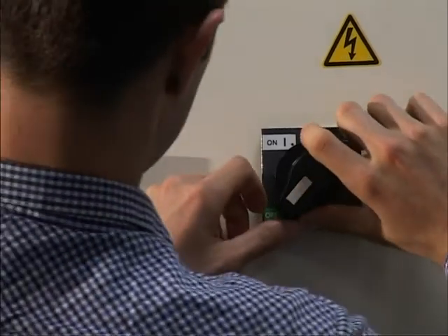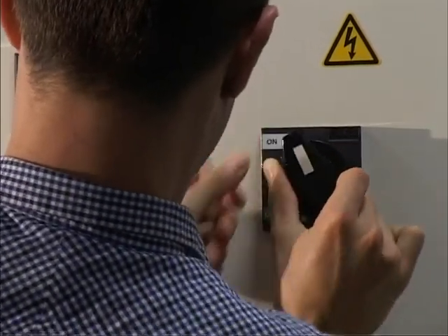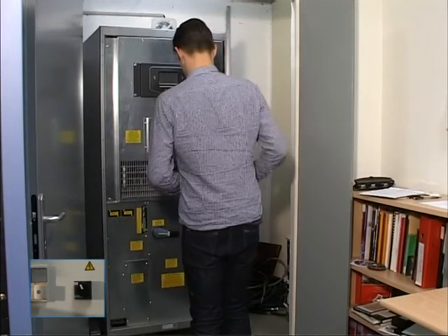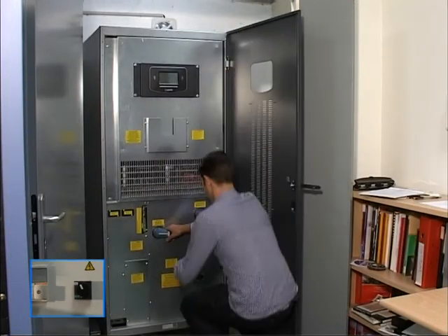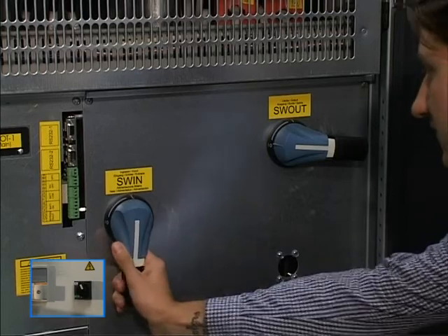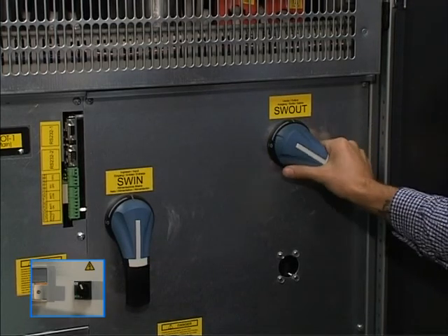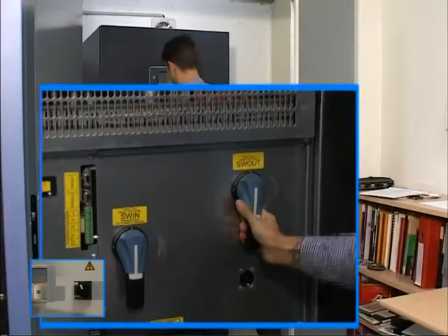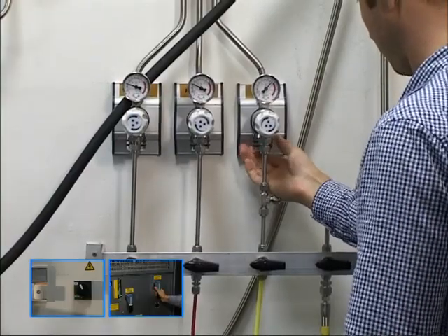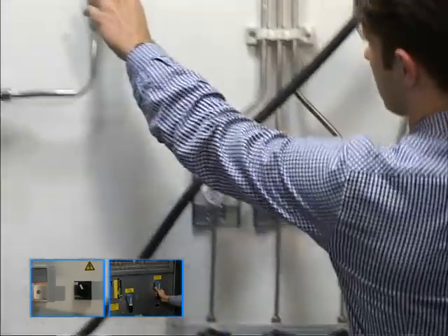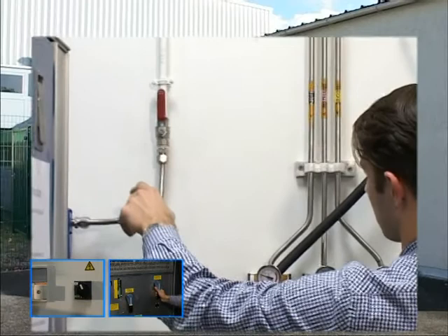To run the torch requires power, gas, and water. Three-phase power must be run through a frequency converter which Chris is turning on right now. Argon is required to start the torch. This is supplied to the room by an external bottle bank and regulated flow is then sent to the flow control manifold.